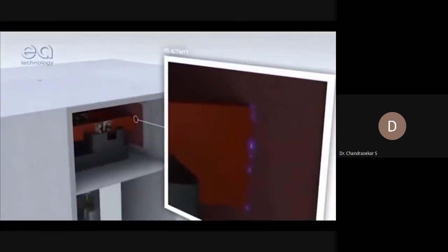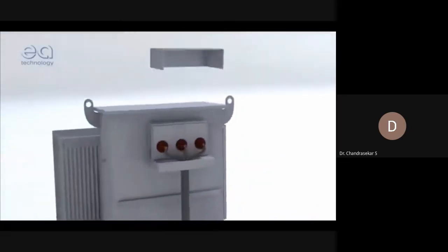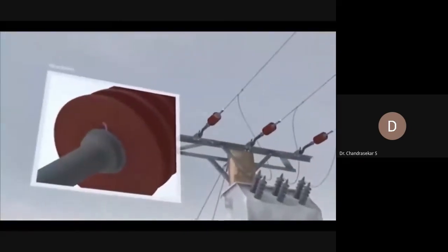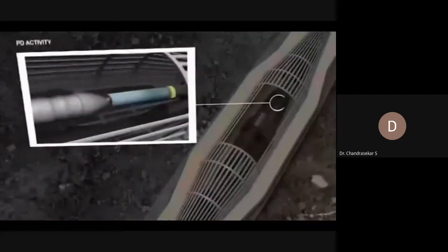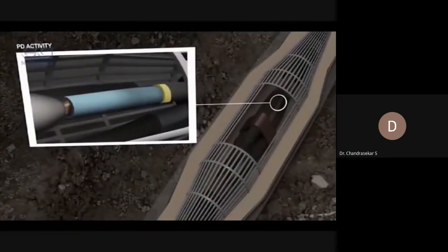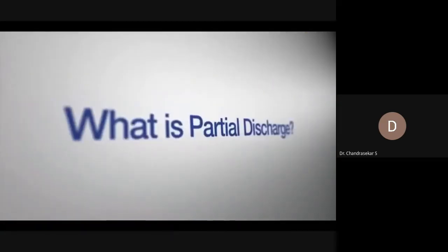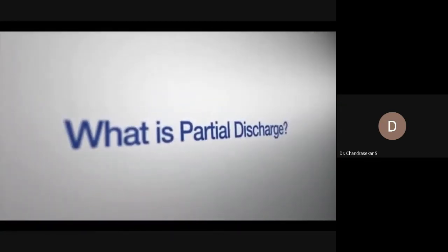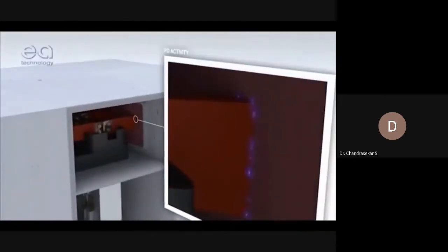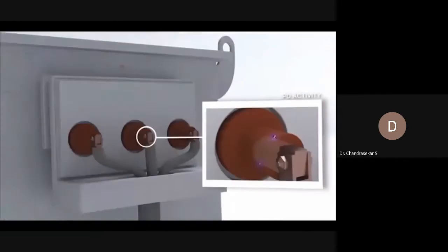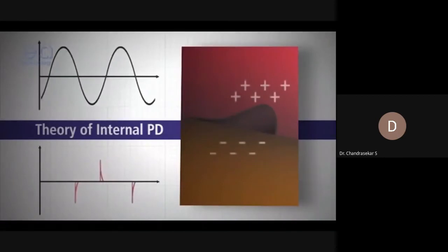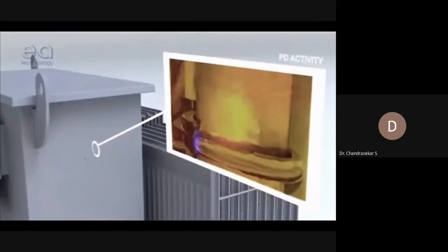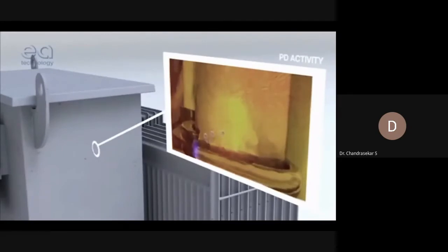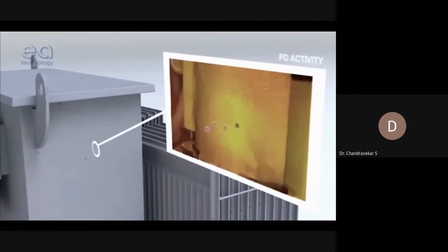Partial discharge, or PD for short, can be found in all types of high voltage assets, from switchgear to transformers, and from overhead lines to underground cables. It causes degradation of assets and can lead to failures. A partial discharge is an electrical discharge or spark that bridges a small portion of the insulation between two conducting electrodes. We call this PD activity, and it can occur at any point in the insulation system where the electric field strength is greater than the breakdown strength of the insulating material.